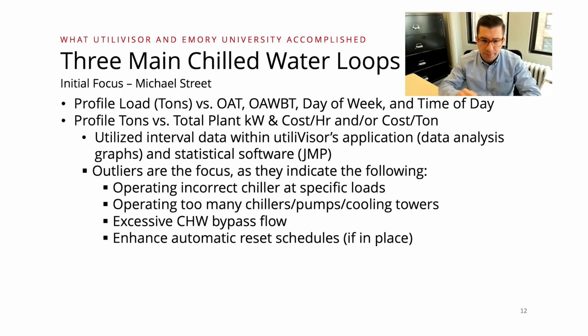I know I talked about this a little bit before, but when we look at these large data sets and scatter plots, it's really the outliers that we first zone in on. Simplistically speaking, you always want to see a nice linear relationship between the amount of cooling that you have and the power it takes to cool those BTUs, or those ton hours. So anything outside that may indicate maybe you're running too many machines, maybe you're running too many auxiliaries. And in this specific case, there was a lot of bypass flow happening, because the engineers were trying to meet the differential of the loop itself, and they also wanted to make sure they were supplying cold enough water from a chilled water standpoint.